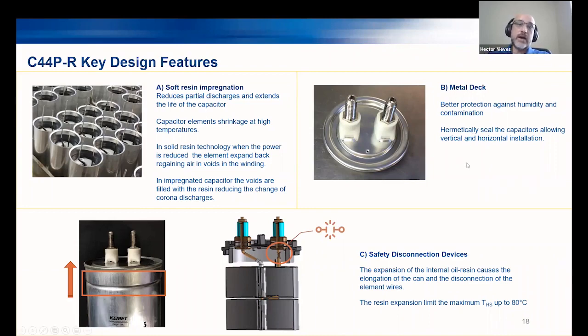So that is one of the advantages of the technology. Now, the other advantage of our technology versus other technologies is that we use a metal deck. In this case, metal deck is a very strong design, completely sealed, versus plastic deck. Plastic deck has the disadvantage that it could absorb humidity. The humidity could go into the plastic. Believe it or not, it will go through the plastic. And we have done some testing in the past, and yes, we noticed that situation. So in the case of metal deck, you are competing with a technology that is better than plastic, but the price is almost close to the level of plastic technology as well. So that is one of the advantages of this capacitor, the hermetical seal.